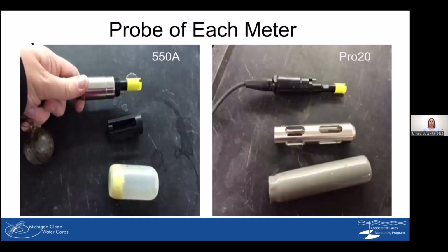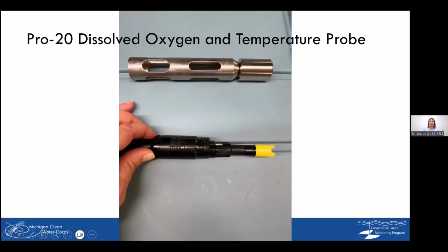This is what the dissolved oxygen probe looks like for each meter. This is the silver part here. This is the probe on a 550A. The probe here is this black portion. The yellow part is a membrane, which I'll go over more in a minute. For the 550A, you have a black protective cage. With the Pro 20, it's a stainless steel piece, and then there's the cap or the cover for each of them, and inside the cap is a piece of sponge. You just can't see through it. This is a little bit more of a close-up for the Pro 20 probe. Right here, this little silver part is the temperature portion, and then this membrane goes over the dissolved oxygen probe to measure dissolved oxygen.